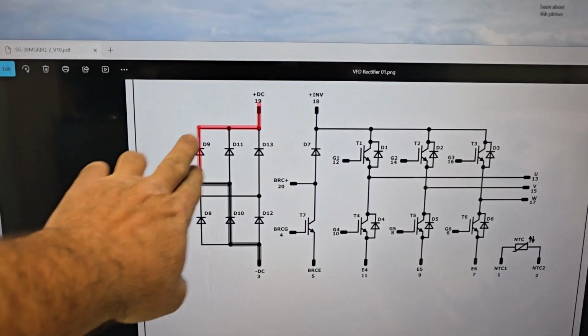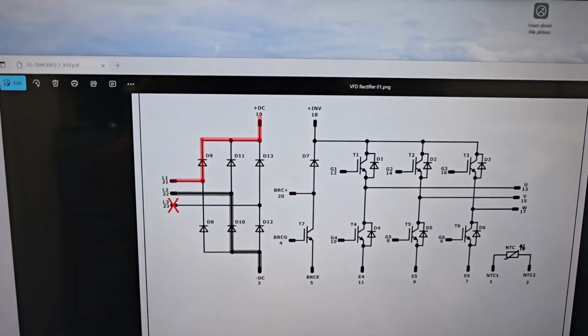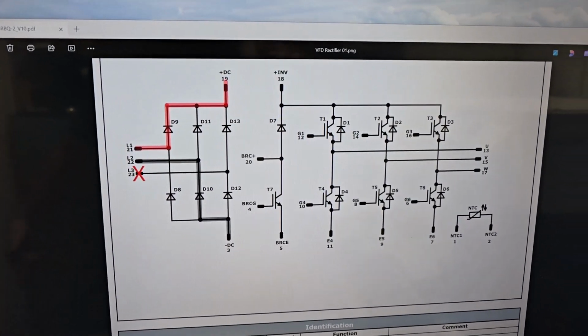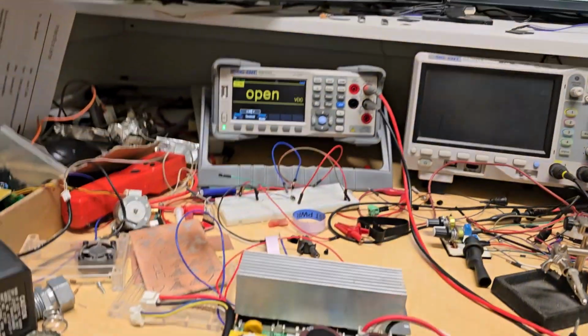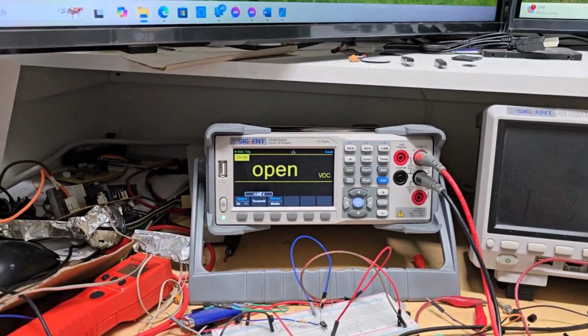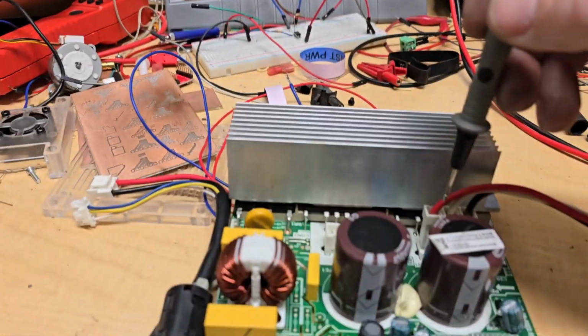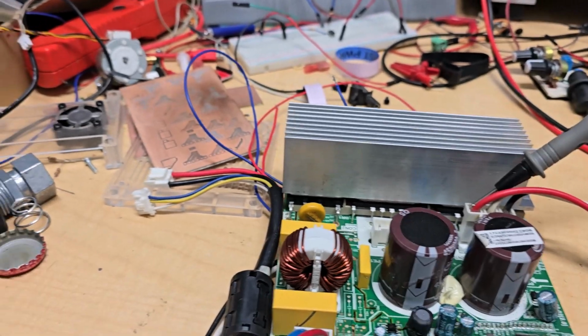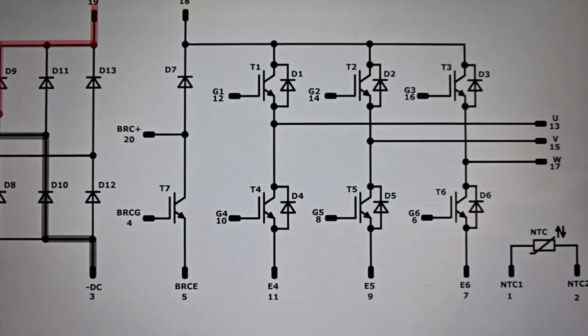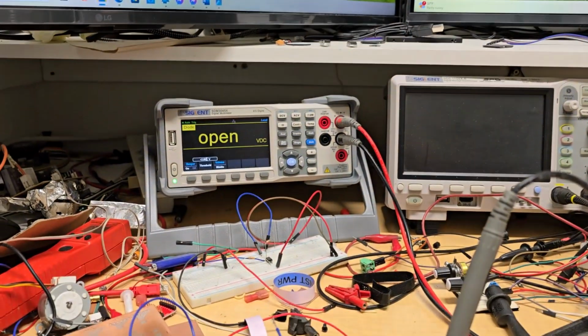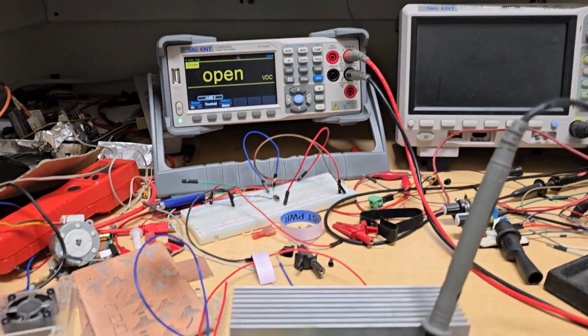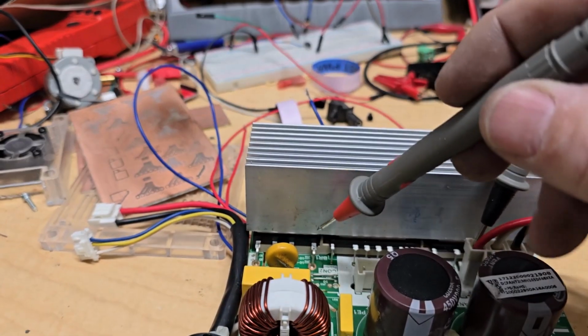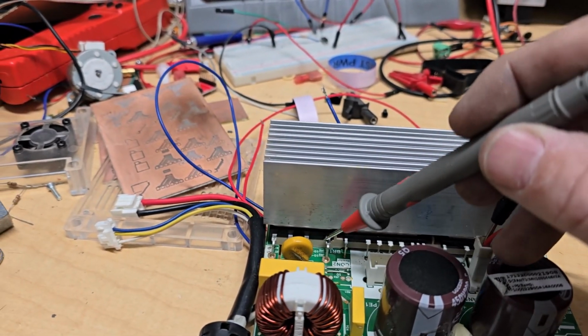So we just got done checking a single phase, going through 4 diodes to check the external rectifier. You could do the same thing, put it in for rectifiers - stick your probe, do your U, V, W outputs. One side you should read like a diode, you're actually just going to read those diodes right there, made for protection, but usually you can tell if your module is probably good.